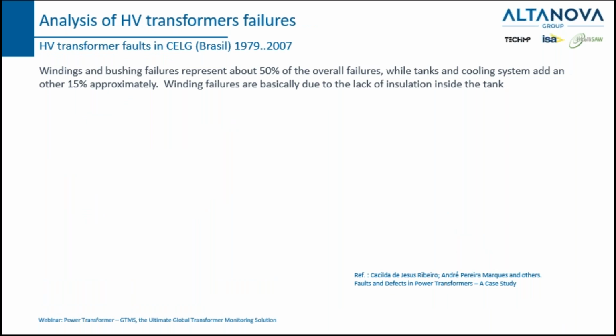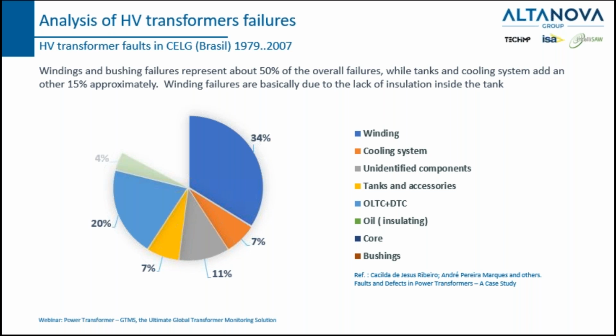Here is another study from CELG from Brazil, now Enel, with some important figures regarding the failure modes. This data has been collected for almost 30 years from hundreds of transformers with problems. We can see that almost 50% of the failures are represented by windings or bushing failures, while tanks and the cooling system add an additional 15% approximately. The reason for the failure of the windings is basically the lack of insulation inside the tank. And with this webinar, we want to share with you our experience in dealing with these numbers.